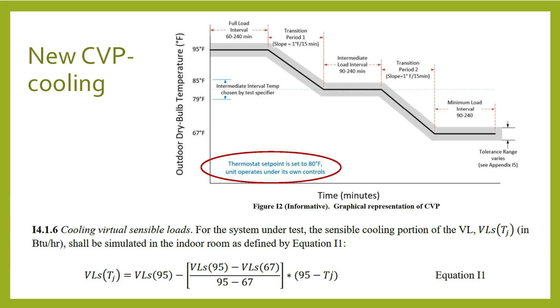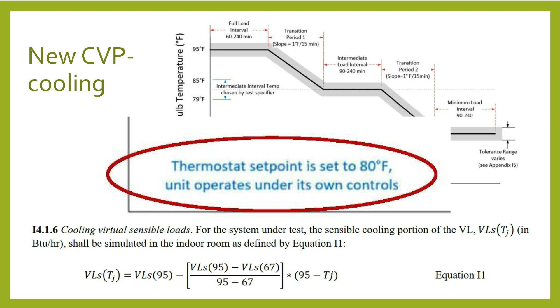So basically this is, actually I'm going to show you, the thermostat set point is set to 80 degrees Fahrenheit. Unit operates under its own controls. This is the load-based test. But instead of doing it at certain points and creating a rating out of it, what they're doing is starting at full load and cooling at 95 degrees, and they're running it long enough to say, all right, we're pretty close to the rating point at 95 within a tolerance, and we're confident that the thing can operate at the capacity that they say in the fixed speed test under its own native controls.